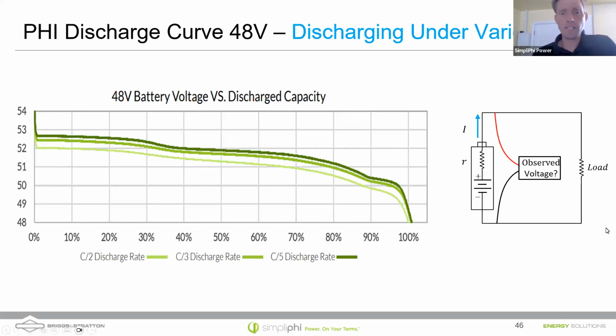When I'm discharging fairly slowly at a 5-hour discharge rate, C/5, I can see the voltage is not that different from a resting charge cycle, but I'll be below 53 volts even when I'm close to 100% state of charge. So it's typically about a volt below on a C/5 discharge curve. And notice when I'm at a 50% state of charge, I'm now slightly below 52 volts. Before I was up at 52.5, now I'm down below 52 for a C/5.